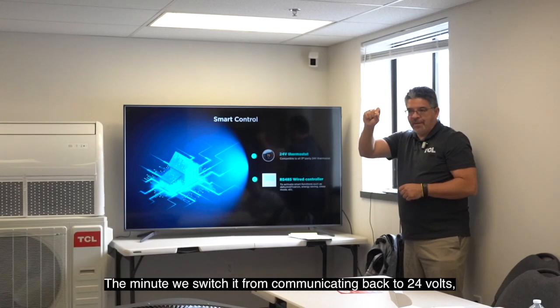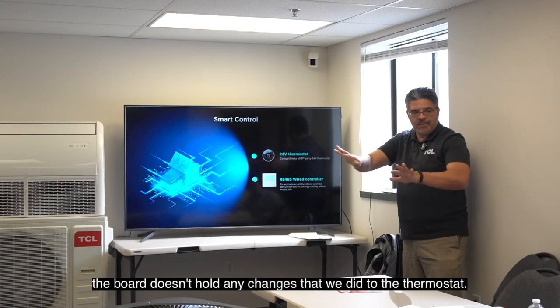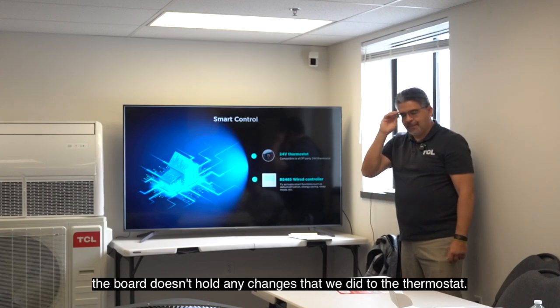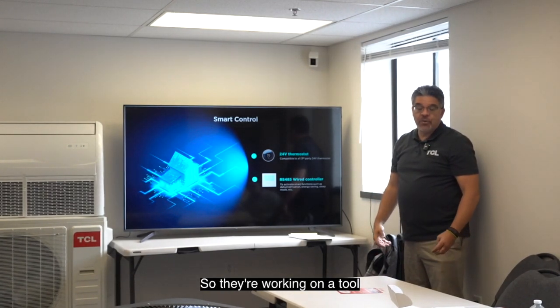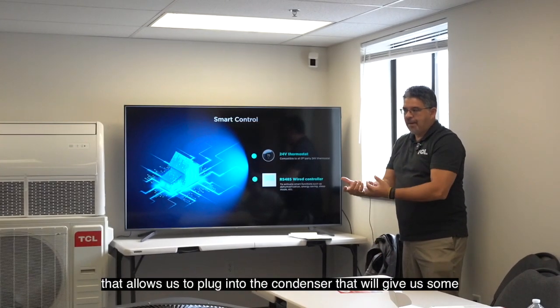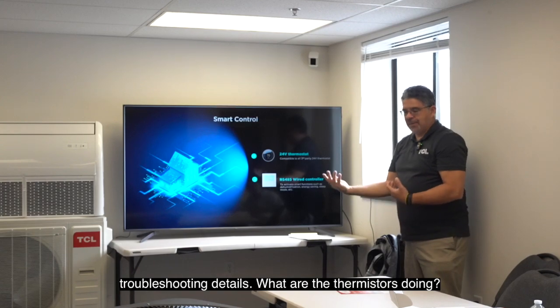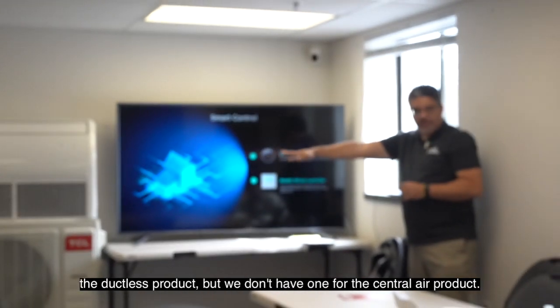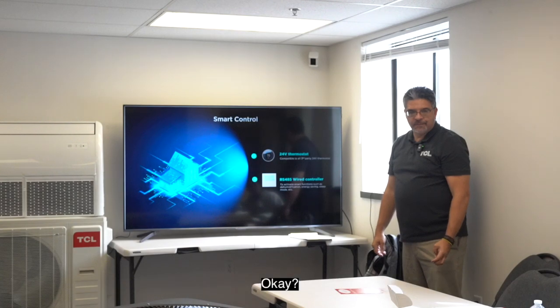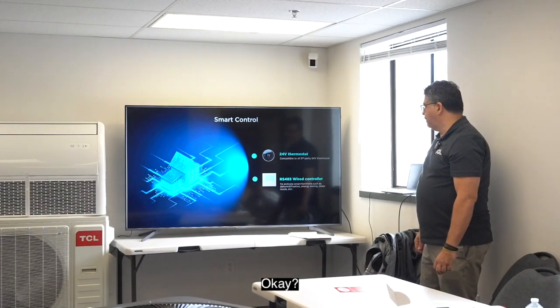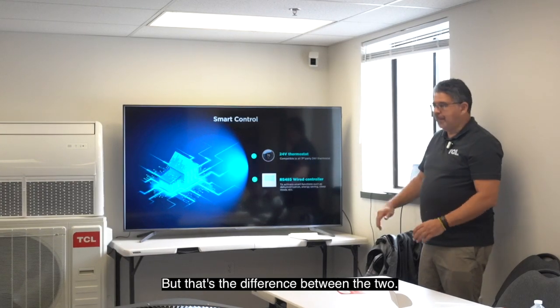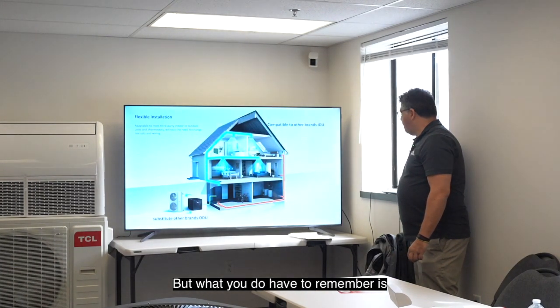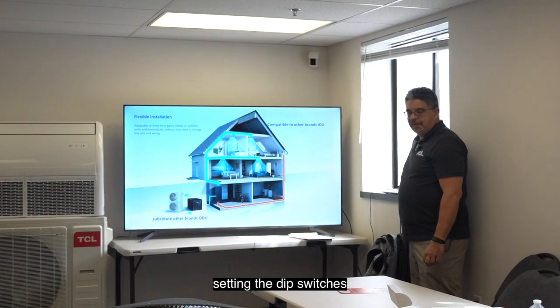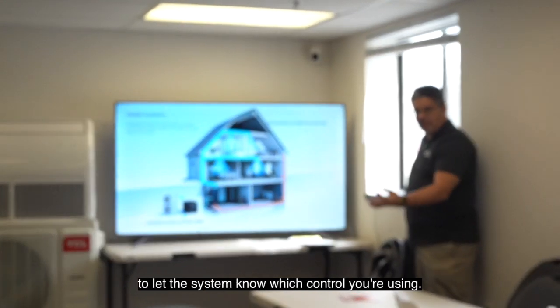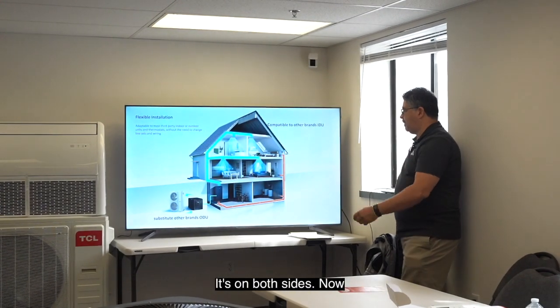The minute we switch it from communicating back to 24 volts, the board doesn't hold any changes that we did to the thermostat. So they're working on that, on a tool that allows us to plug into the condenser that will give us some troubleshooting details. What are the thermistors doing? What's the compressor operating at? Things of that sort. We have a tool for the ductless product, but we don't have one for the central air product. Okay? But that's the difference between the two. Okay? But what you do have to remember is setting the dip switches to let the system know which controller you're using. All right, it's on both sides.